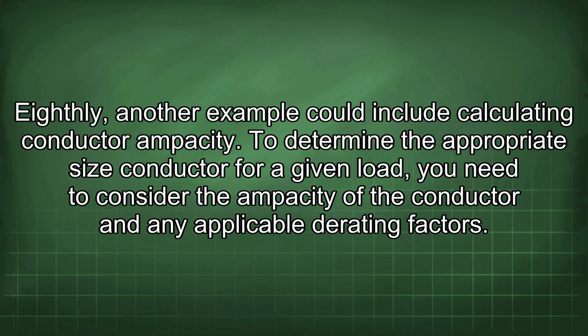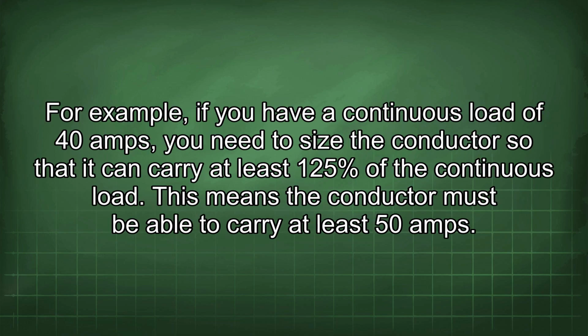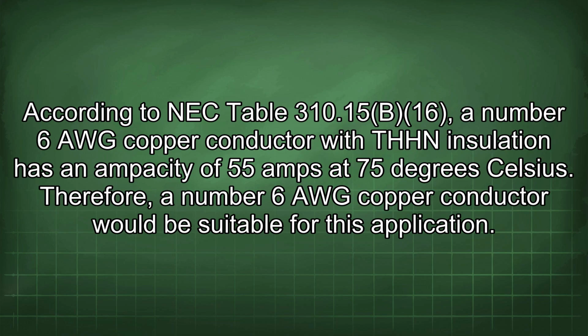To determine the appropriate size conductor for a given load, you need to consider the ampacity of the conductor and any applicable derating factors. For example, if you have a continuous load of 40 amps, you need to size the conductor so that it can carry at least 125% of the continuous load. This means the conductor must be able to carry at least 50 amps. According to NEC Table 310.15(B)(16), a number 6 AWG copper conductor with THHN insulation has an ampacity of 55 amps at 75 degrees Celsius. Therefore, a number 6 AWG copper conductor would be suitable for this application.